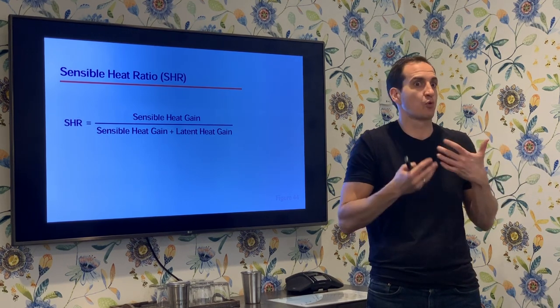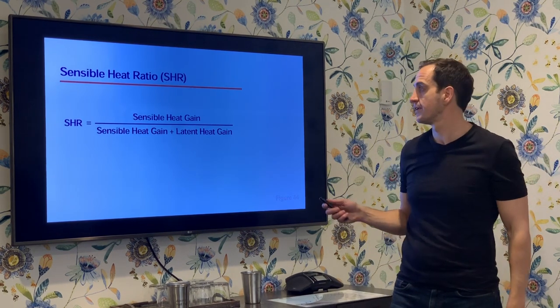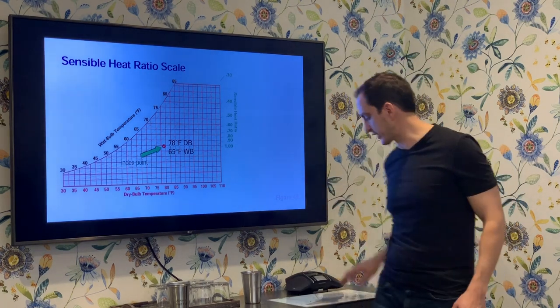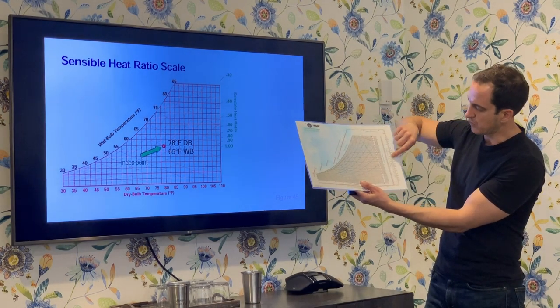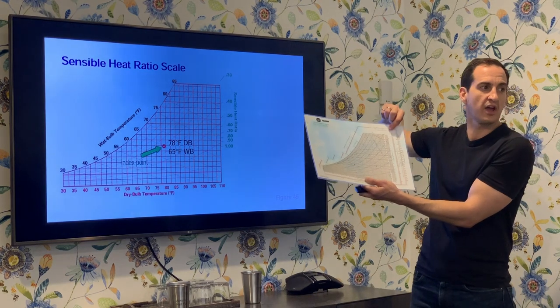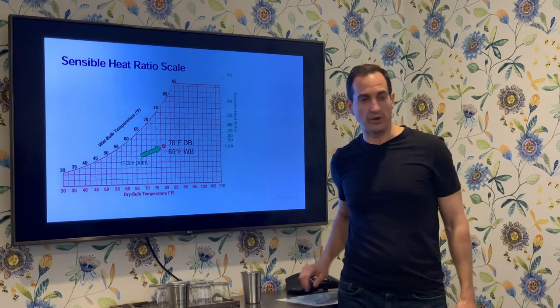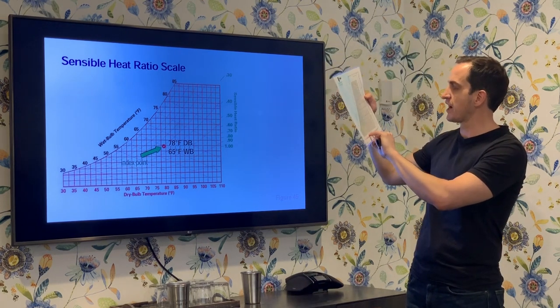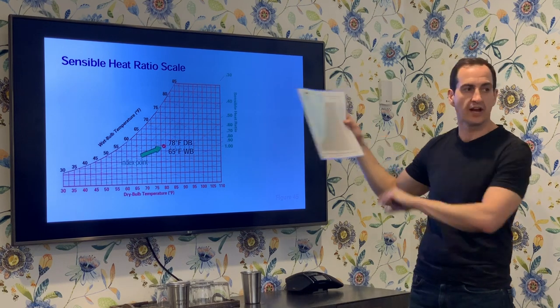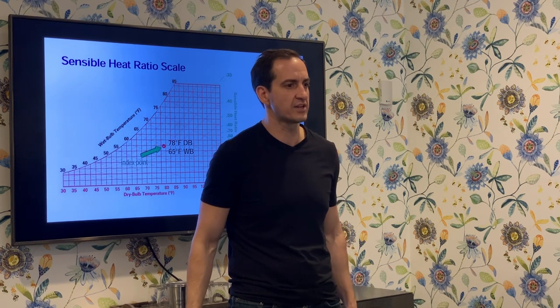There is a way to take both types of energy addition and express them in the same common unit, giving us a ratio of how much energy to remove is sensible versus how much is latent. On your chart you'll notice the sensible heat ratio scale around the outside of the chart. It is all referenced to an index point — a little dot you'll find in the middle of the chart. That dot is at 78°F dry bulb, 65°F wet bulb, 50% relative humidity.